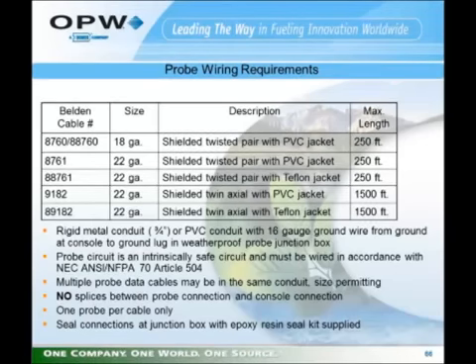The probe wiring requirements. The probe wiring requirements change according to the distance between the probe itself and the TLM Interface Module. There are 4 different types of cable that we specify for up to 250 feet. That's the 8760 and the 88760, 8761 and the 88761. The difference between the 8760 and the 88s is that the 8760 is a PVC jacket and the 88760 is a Teflon jacket, the same with the 61. For distances between 250 feet and 1500 feet, the two cables specified are the 9182 and the 89182 cables. These are larger cables for longer distances. Equivalent cables can be used.